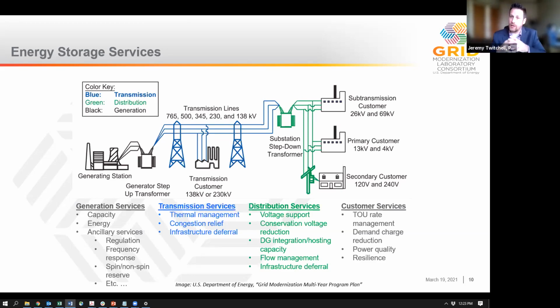Moving to the transmission side, we can use energy storage to do thermal management on the transmission system, making sure the lines operate within their prescribed limits. We can do congestion relief. If we have a load pocket with inadequate transmission to meet it, we can put energy storage inside that load pocket, charging it during low demand periods and using it during high demand periods when we don't have enough transmission to meet the load. By doing that, we can defer additional investments in transmission.